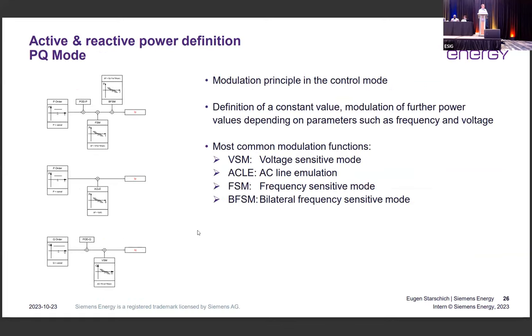One of the key features, if we are talking about the PQ, active power, reactive power control mode, is a modulation principle of the control mode. That means the operator defines a certain amount of power to be transmitted. Let's say we have a 1000 megawatt system. I say, okay, I want 700 megawatts constantly transmitted, and then I have modulation functions. What does it mean? I have a 300 megawatt capability, which might depend on network conditions.